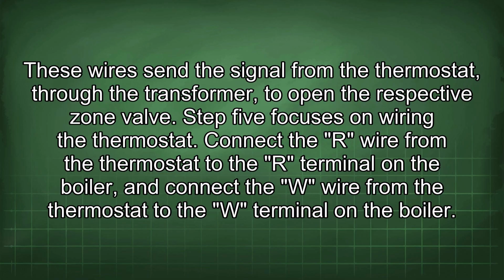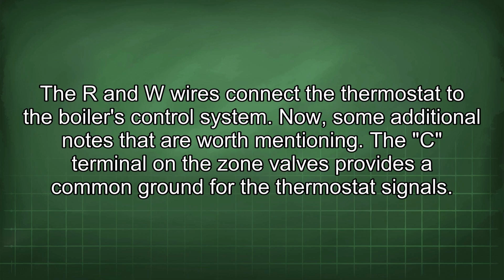Step 5 focuses on wiring the thermostat. Connect the R wire from the thermostat to the R terminal on the boiler, and connect the W wire from the thermostat to the W terminal on the boiler. The R and W wires connect the thermostat to the boiler's control system.